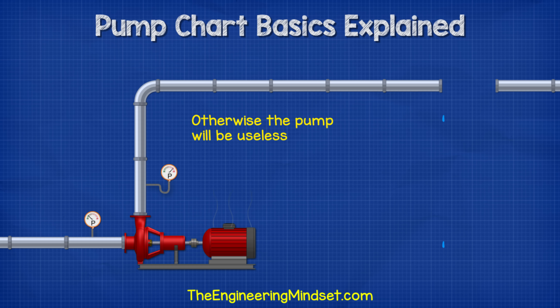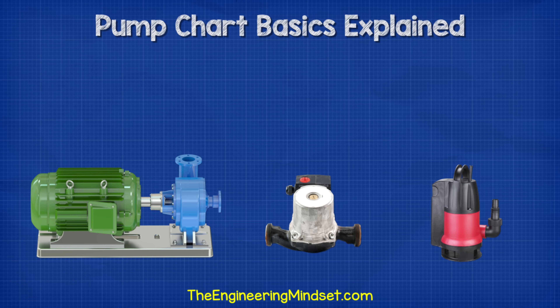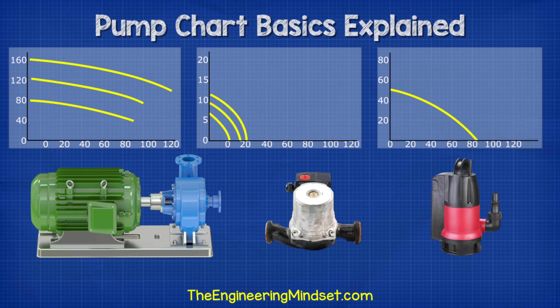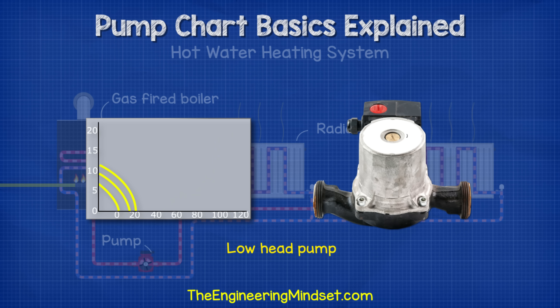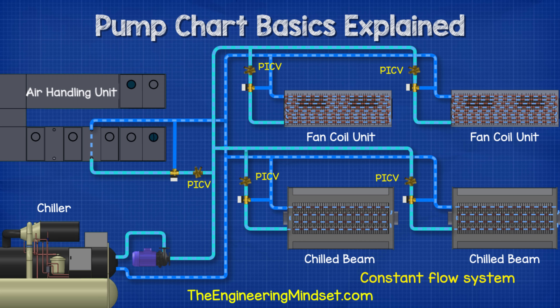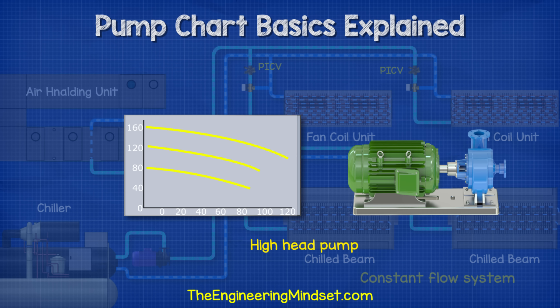Otherwise, we're not going to get any liquid out the other end. When we look at the pump charts, we'll find pumps ranging in head and flow rate. For example, when we look at a small domestic heating system, there are few fittings and short pipes, so we would use a pump with a relatively low head pressure. But if we were to look at a commercial heating system with multiple air handling units, fan coils and long pipe lengths, then we know the pressure drop will be much higher, so we would need a pump that can provide much more head pressure.